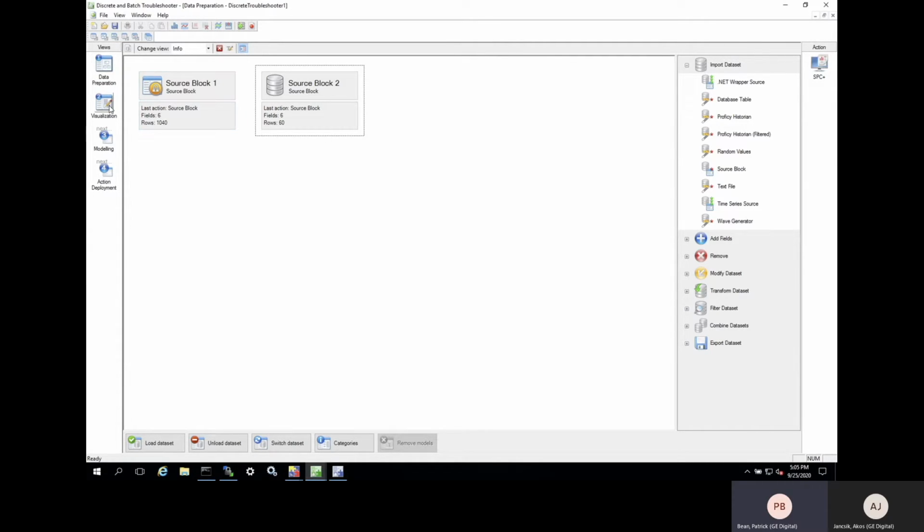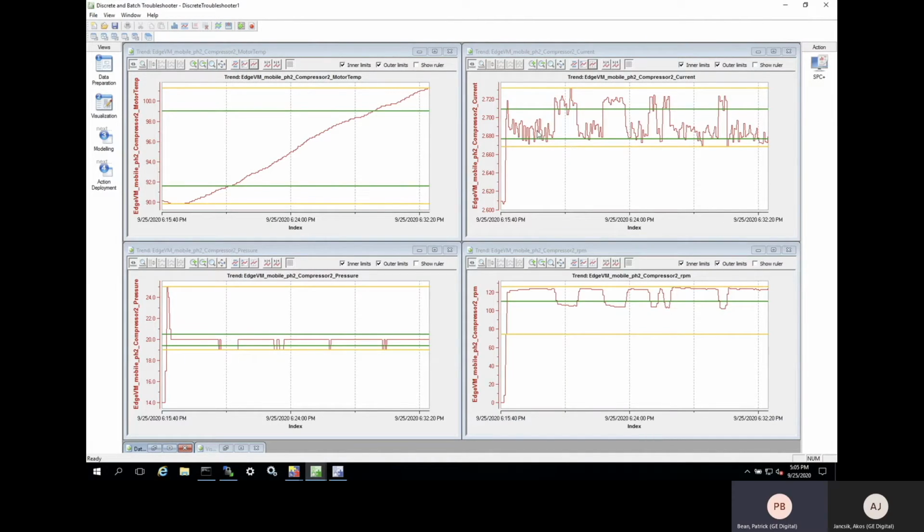Now, after pulling all the right tags for that specific pump into our app, we can visualize our data. And when we do this, the findings jump right off the page. As you can see here, slight deviations in the current readings that just perfectly align with small drops in RPM. Small drops that are too small to be detected by the OEM recommended alarm limits. And also, as we expected, the output PSI, which is the target, deviates just ever so slightly and remains undetected with good quality. Surely this is that something that doesn't sound or feel right that our shift supervisor described at the beginning.